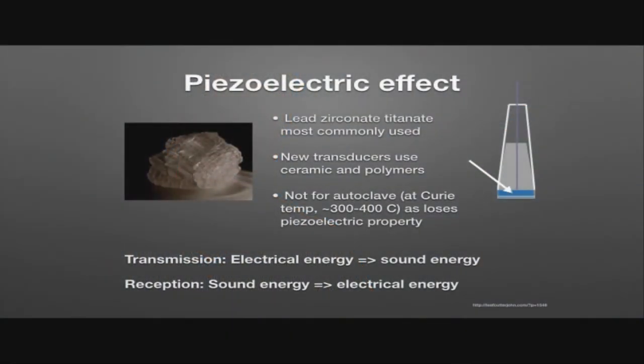One of the main components of the ultrasound probe is the crystals. These are the piezoelectric crystals, typically made from lead zirconate titanate, though newer transducers use a ceramic polymer construction. Whether older or newer, the important thing to remember is that you cannot autoclave these — sterilizing them at 300 to 400 degrees Celsius will deform the crystal and destroy their piezoelectric properties. Most importantly, these crystals can both transmit and receive sound energy — they are bi-directional energy converters — and that's how we form the ultrasound image.